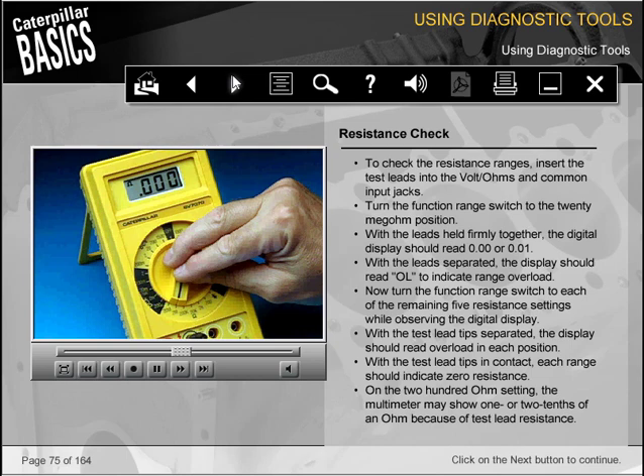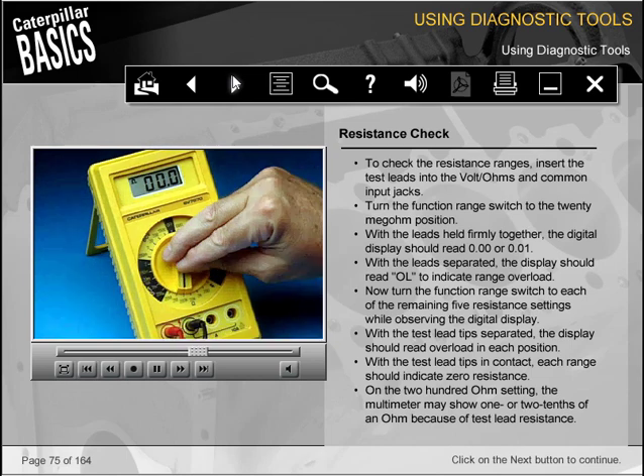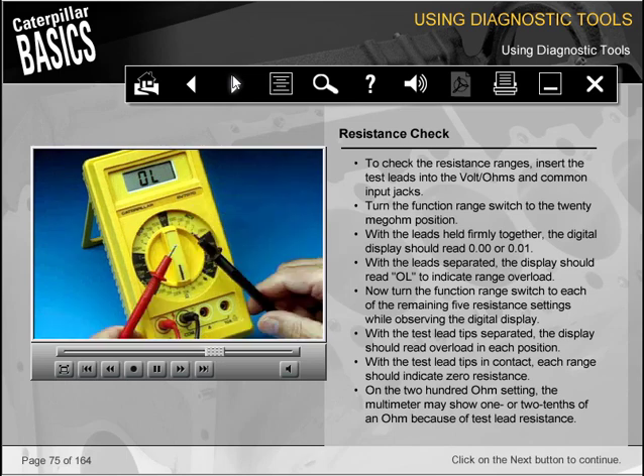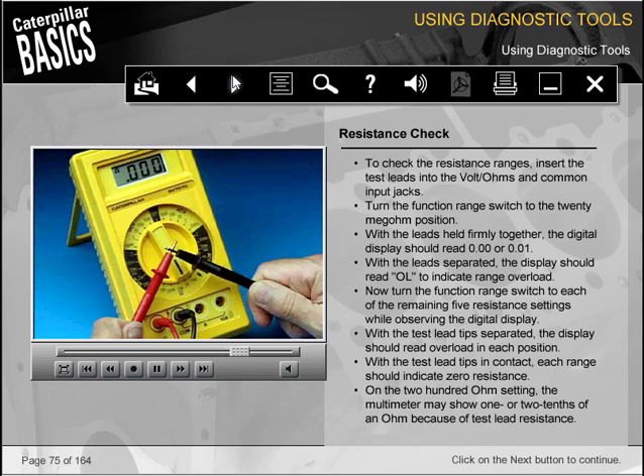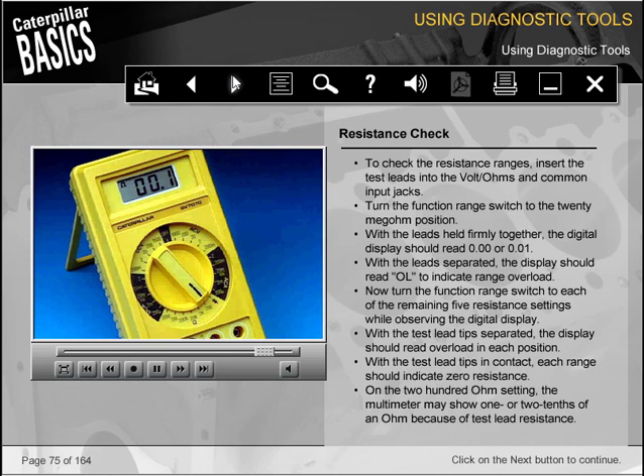Now turn the function range switch to each of the remaining 5 resistance settings, while observing the digital display. With the test lead tips separated, the display should read overload in each position. With the test lead tips in contact, each range should indicate 0 resistance. On the 200 ohm setting, the multimeter may show 1 or 2/10 of an ohm because of test lead resistance.